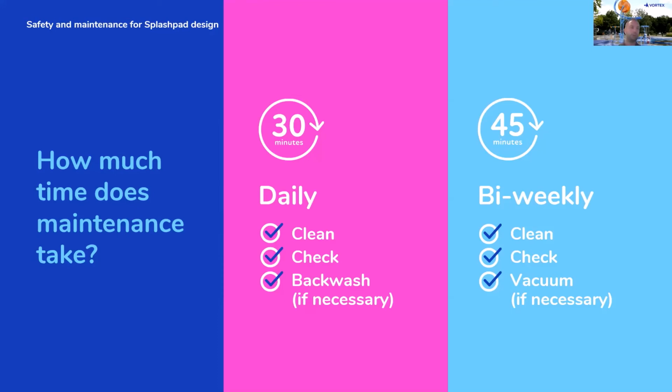With the use of a blower, a system with one drain can typically have all daily maintenance procedures completed in about a half an hour. This includes cleaning the play surface, cleaning the deck drains, checking your pH, chlorine, alkalinity, and calcium hardness. Again, chemicals should be tested and logged. You're going to want to keep a log. I know it's a little bit of a pain, but please keep a log day in, day out of where your chemical readings are at. Checking that UV dosage, just to make sure your UV isn't about to fail and you don't need a new bulb. And backwash sand filters if necessary.